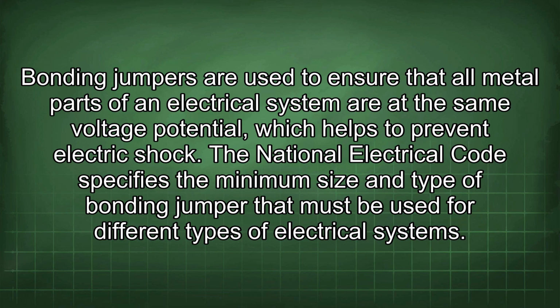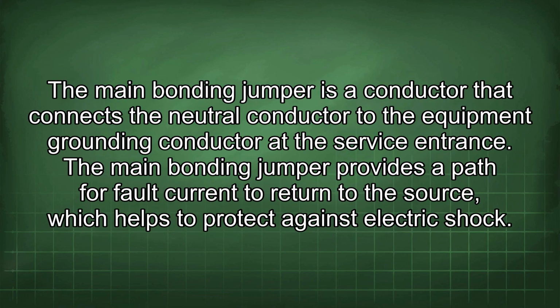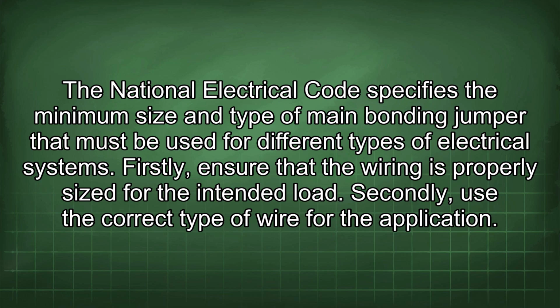of electrical systems. The main bonding jumper is a conductor that connects the neutral conductor to the equipment grounding conductor at the service entrance. The main bonding jumper provides a path for fault current to return to the source, which helps to protect against electric shock.